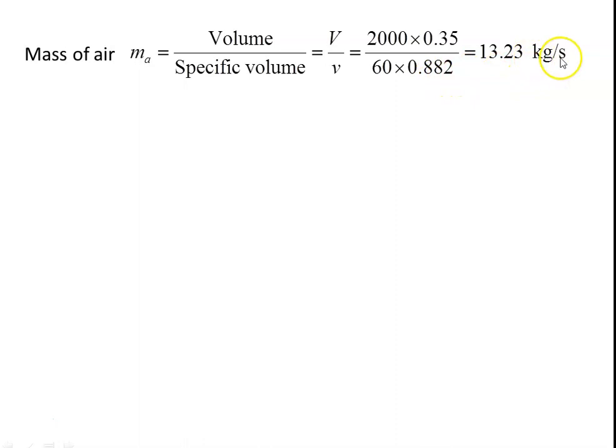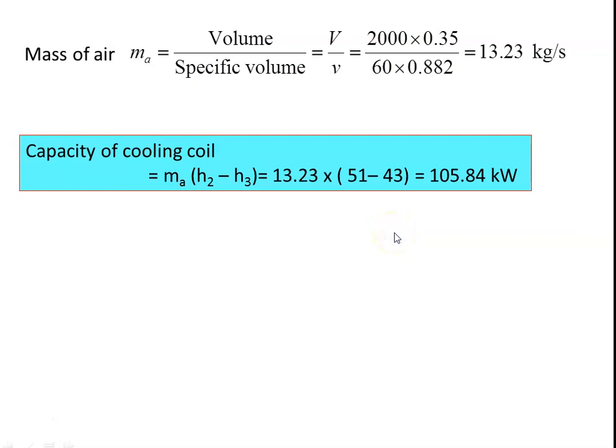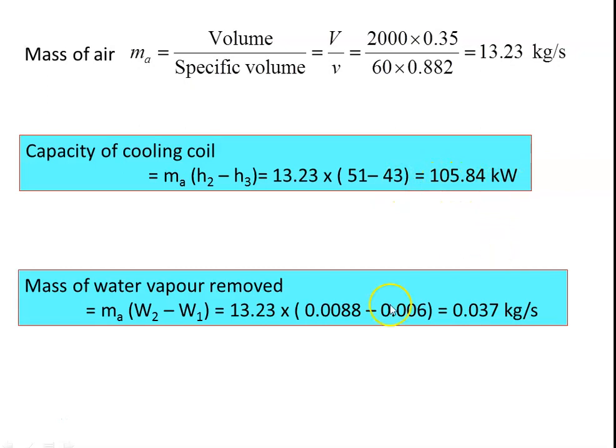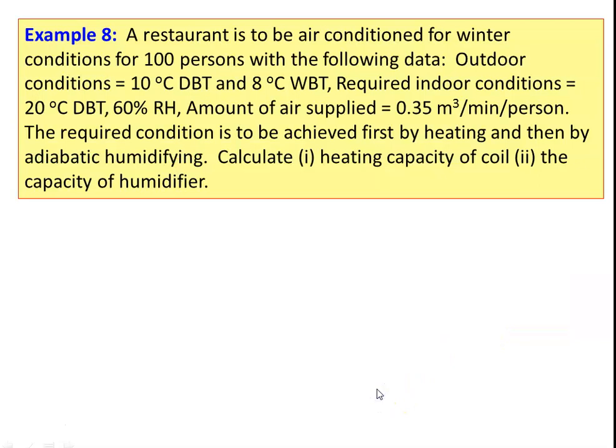Mass of air = 2000 × 0.35 / 60 / 0.882 = 13.23 kg/s, which is the total quantity of air circulated. Capacity of cooling coil = ma × (h2 − h3) = 13.23 × (51 − 43) = 105.84 kilowatts. Mass of water vapor removed = ma × (w2 − w1) = 13.23 × (0.0088 − 0.006) = 0.037 kg/s.